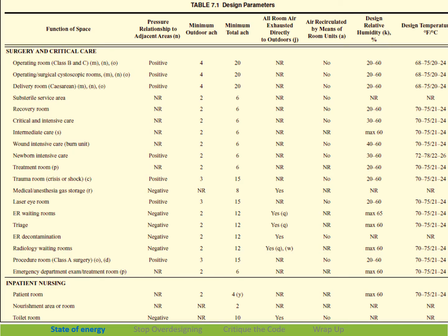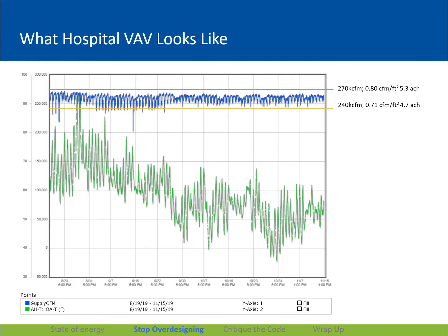And then this is why we have so much reheat. We design hospitals with a legacy methodology called air changes per hour. There's a table that tells us how many air changes to use for nearly every space. This design method drives our energy use. And I don't know if you've ever met any design engineers, but nobody designs right to the code minimum. We design over these minimum numbers, and then we have this nasty habit of running spaces in hospitals 24/7, which creates a tremendous amount of reheat above this. So first thing we need to do is stop over designing, stop overflowing air.